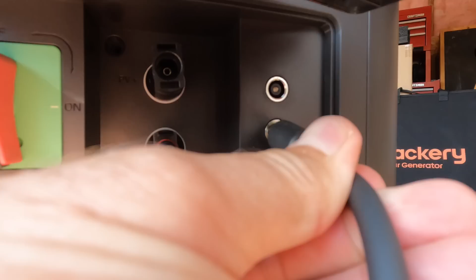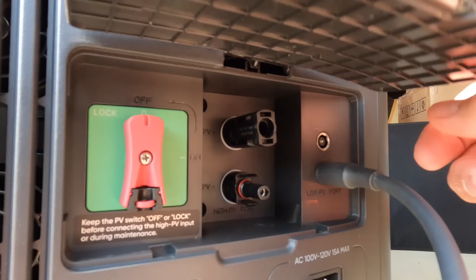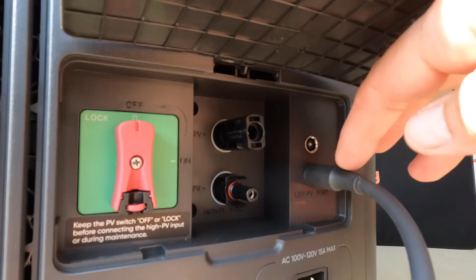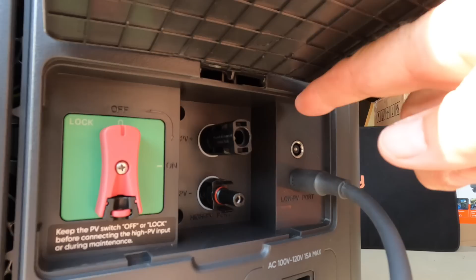Open up our DC input panel. We can see our low voltage PV inputs right here. I'm going to plug one in, get it completely plugged in. Let's check, and we're still on low voltage, right? Our high voltage is off, so we're not using the high voltage MC4, which is for 4,000 watts. We can go 500 to get 1,000, or 600 to get 1,200. We've got 500 coming in right now on this low voltage.